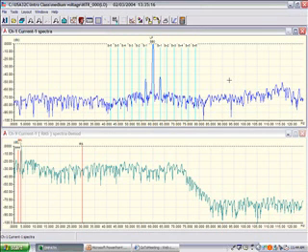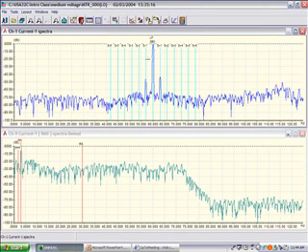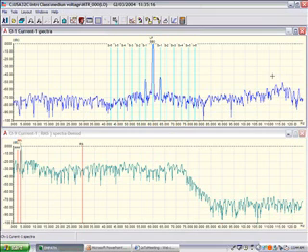If I have multiple peaks on either side, that usually indicates something happening outside the motor. Because what you'll also find as you go through electrical signature analysis is around this line frequency, everything related to the rotor will occur. So, if I have a varying speed or pulsating load or something else occurring on the outside of the motor, this peak will have a very broad base.